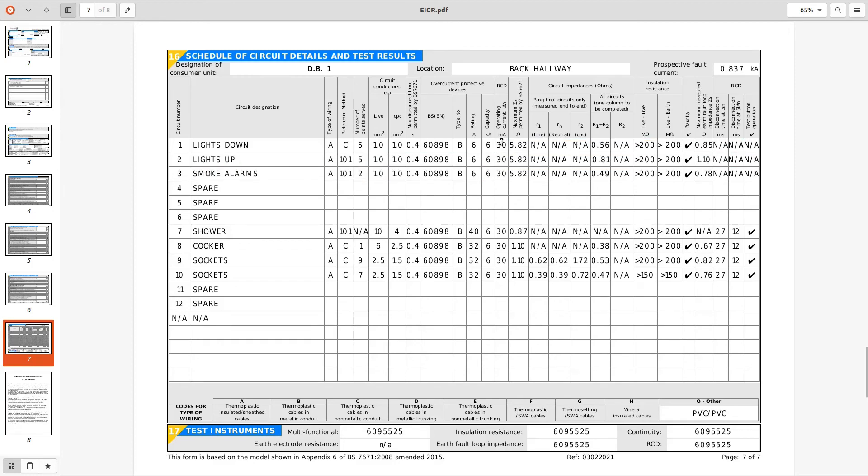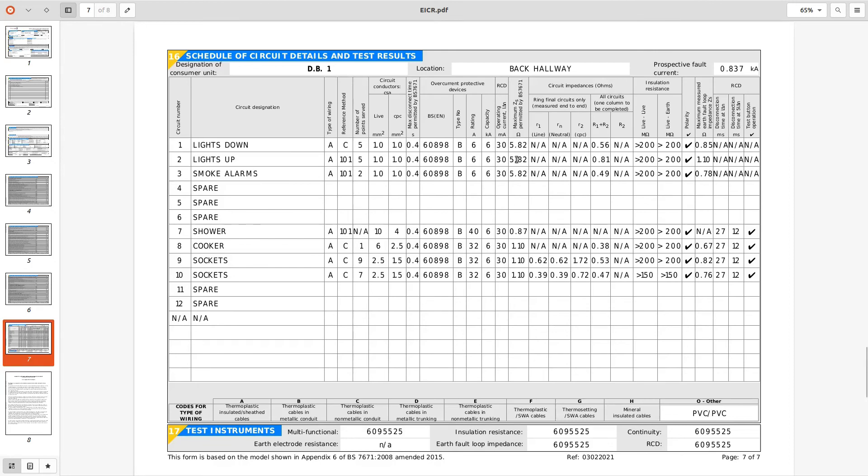Let's have a quick look, any significant errors on here. Oh 30 milliamp RCD protection on this column here for circuits one two three which is a bit odd because he's got no test times for them, maybe he's just put that in by accident. But he did take that they were protected by RCD for I would assume lights upstairs, I'm really confused at this point. Maximum permitted Zs values are incorrect, he's done 80% values in here and it's asking for the maximum Zs permitted by BS7671. So you need to be picking them pages from that page 61 in the regs book and the 18th edition.